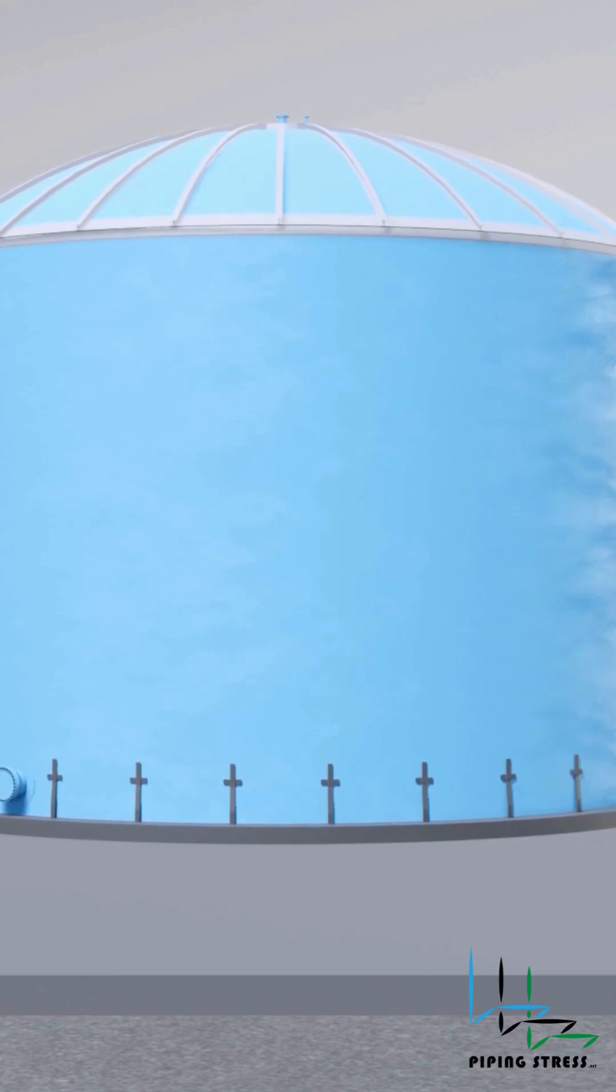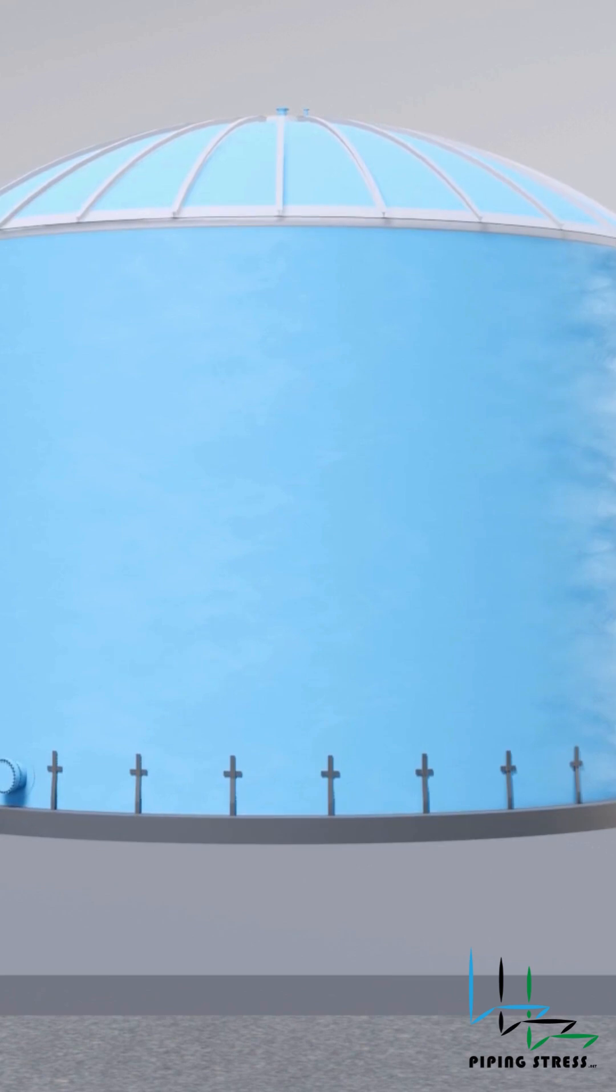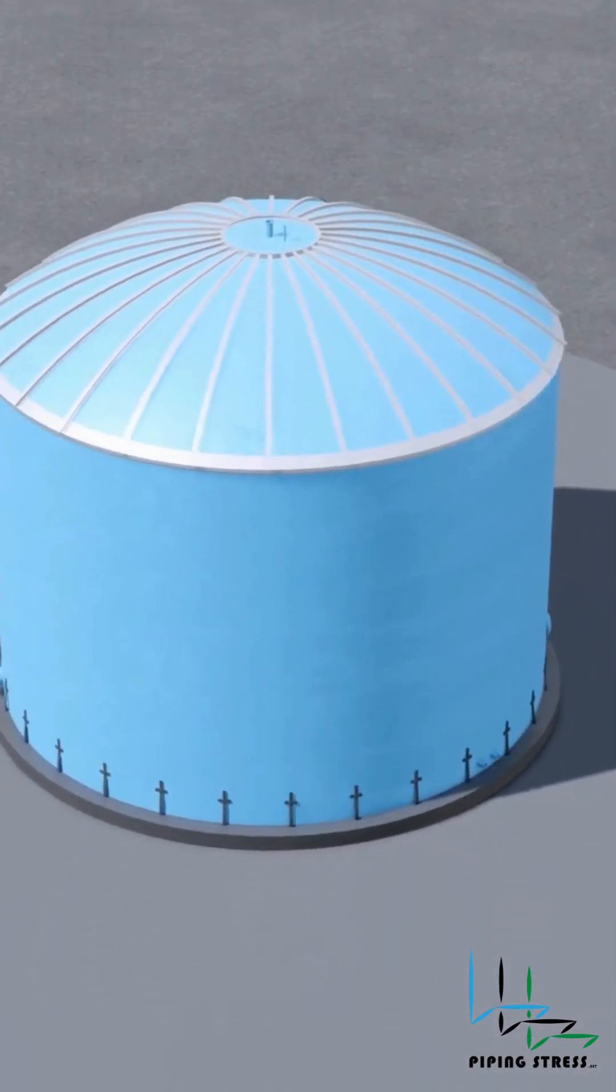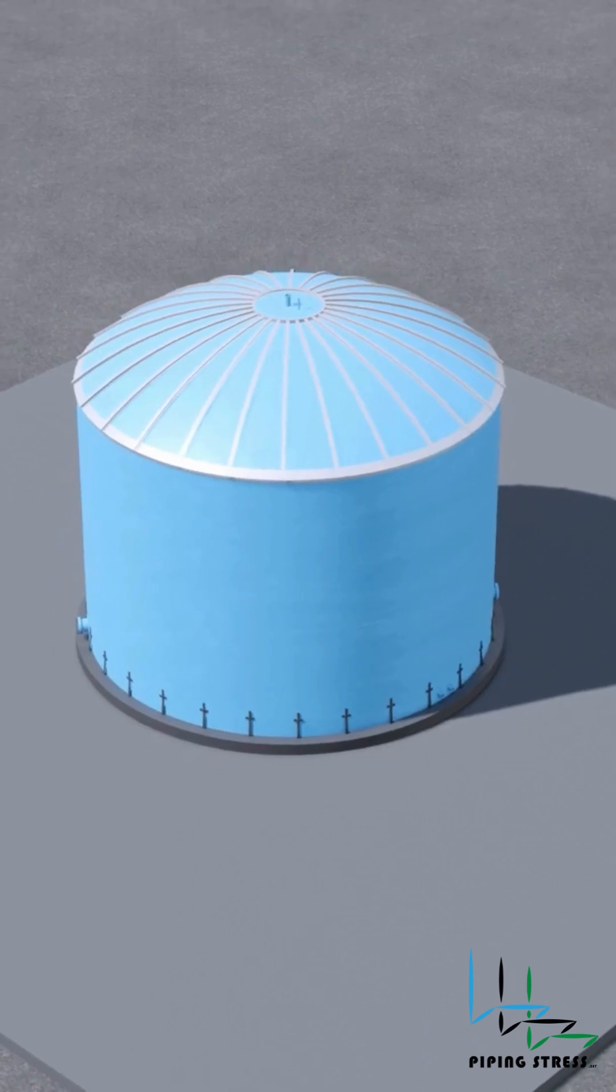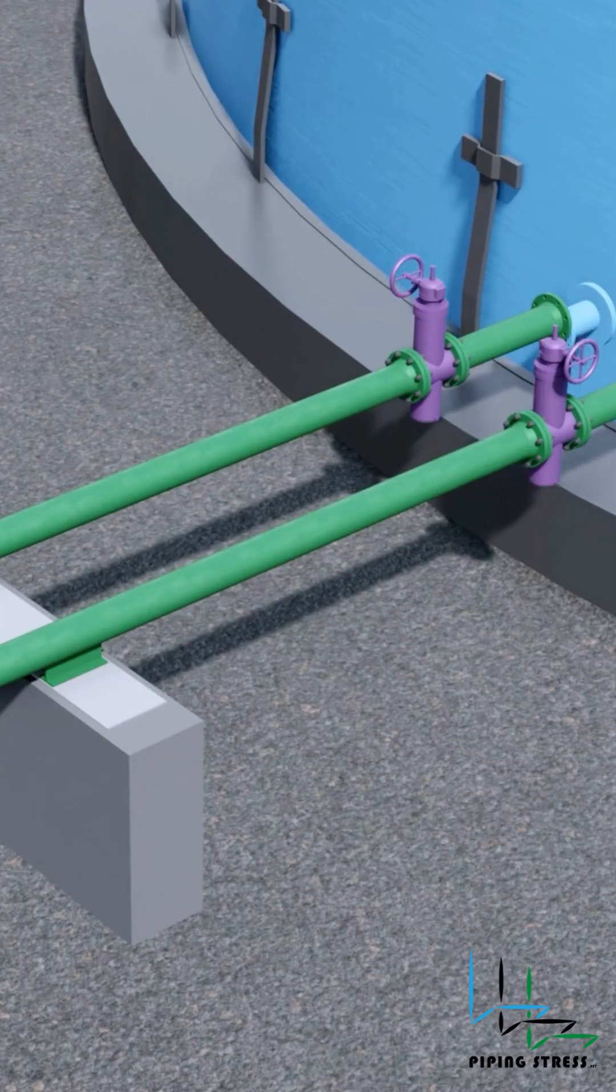During the hydrotest operation, one-third of the settlement occurs while the rest happens throughout the tank's lifespan. Due to this, the piping connections must be removed during the storage tank hydrotest operation.